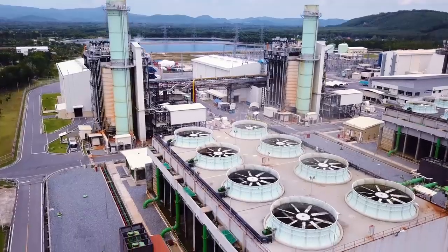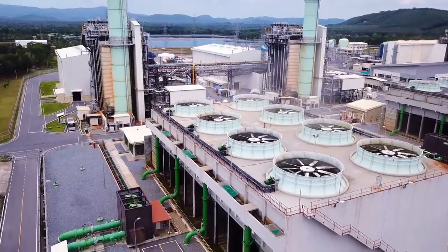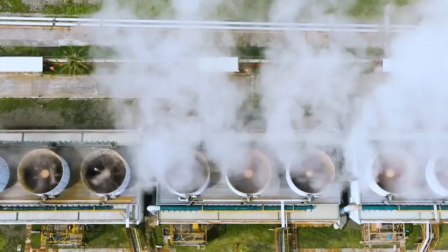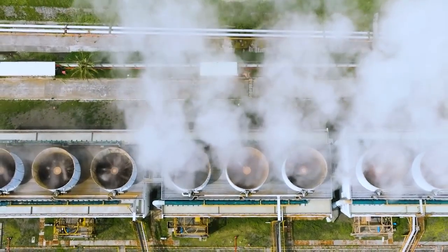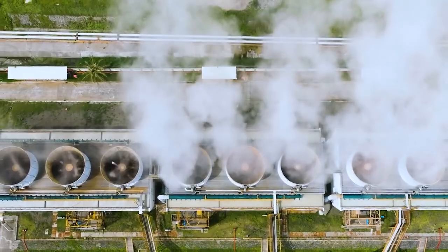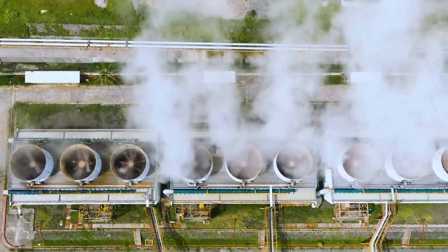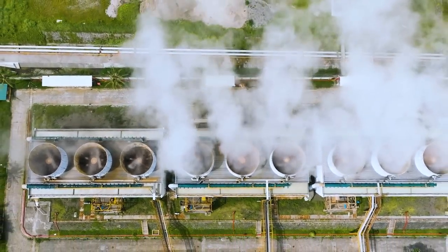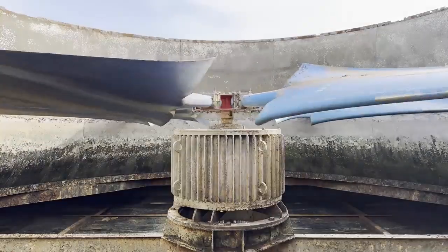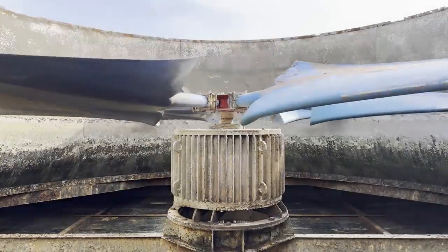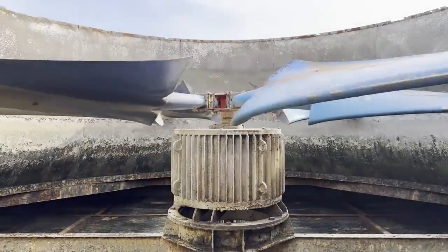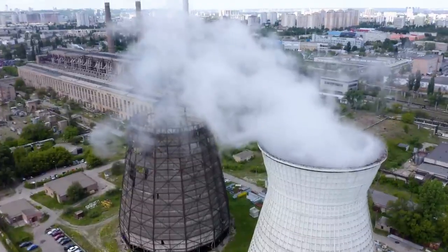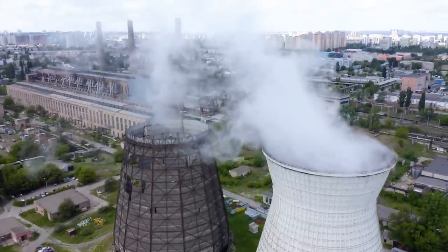And in fact, lots of power plants, refineries, and chemical plants use mechanical draft cooling towers as well. They're less dependent on ambient conditions to create the necessary airflow. They're smaller, usually less expensive to build, and offer some flexibility if heat loads fluctuate. And not all cooling towers use evaporative methods. Dry cooling towers just use heat exchangers inside with the cooling water flowing in a closed loop. In dry systems, you're limited by the higher dry bulb temperature instead of wet bulb, but you don't lose any water to evaporation, and you don't have to deal with the buildup of minerals that happens in wet systems as cooling water evaporates away.